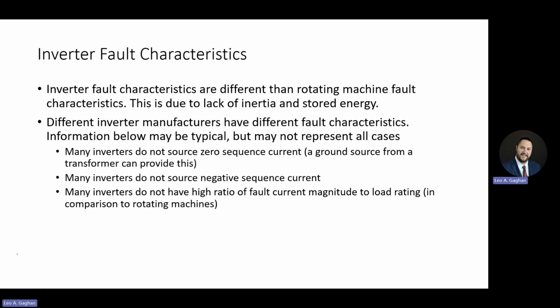So, some inverter fault characteristics. The fault characteristics are a lot different than rotating machine characteristics. The big difference here is the lack of inertia and stored energy. It also has a lot to do with the fact that what's driving these inverters is based more on programming, software and firmware, than it is on the power electronics, based more on all of those things than just natural laws of physics, which is what drives our conventional thought process with symmetrical components, things like that.